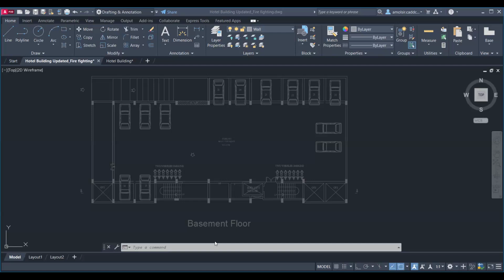Let us start with the placement, maximum distance 15 feet. Pendant is not directly installed in pipe. Why not pendant? Ceiling will be required for placement, and we are not having any false ceiling in the basement, that's why. So I think upright for the basement, sorry for the interruption. For the pendant we need to install flexible pipe, right? Flexible pipes will be installed accordingly, but it will require a ceiling for hosting also, for hosting purpose. Yeah, so that's why upright will be the best case here.